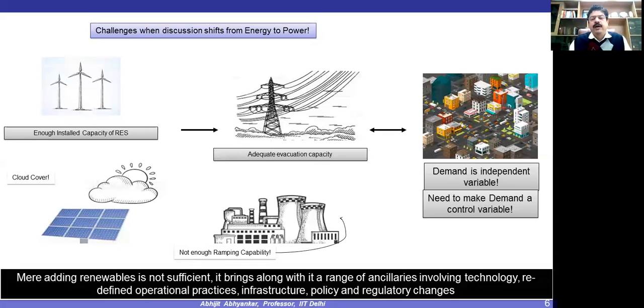It could be 50 megawatts, 100 megawatts, or more. Once the cloud passes, that generation gets injected back into the grid. So long as the changes are small, whether solar generation comes into the grid or goes out, those can be handled with the inertia of rotating masses. But if the changes are large, you will have to ask the conventional generators, or other sources of generation, to do ramping.